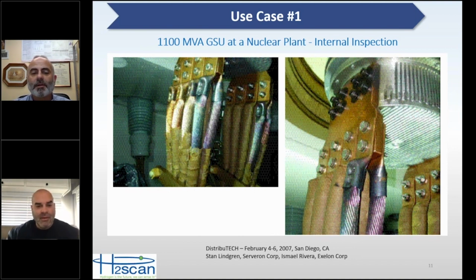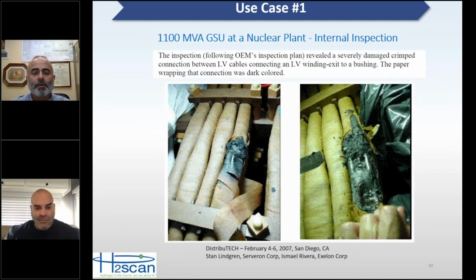The other issue they found, if we go back to the prior slide, is that they had wrapped too much paper around those leads. In order for the conductors and those crimp connections to stay cool, the oil has to fully impregnate the paper. If the oil doesn't fully impregnate the paper, then the oil is not pulling the heat away from the conductor. Now what you've created is insulation to keep that heat in, and that was enough to completely burn away the paper until there was no paper left. Once you lose your paper, you've lost your insulation, and it started arcing. And so, of course, our online DGA monitor was able to watch that in relatively real time. Okay.